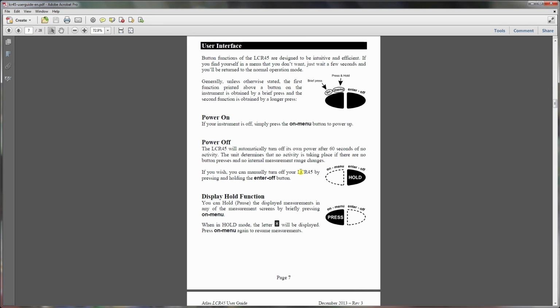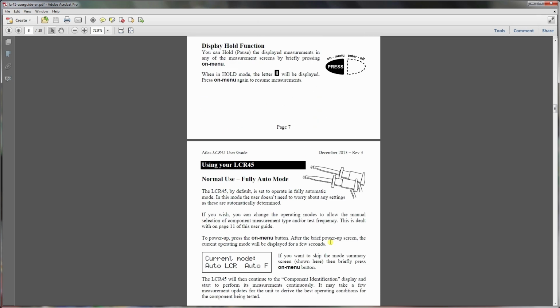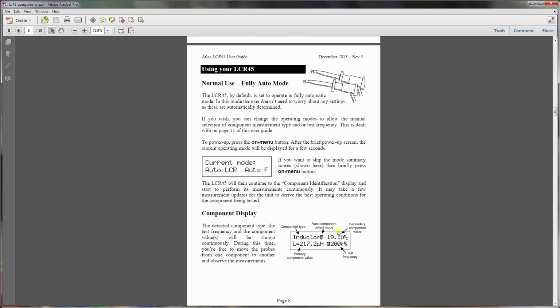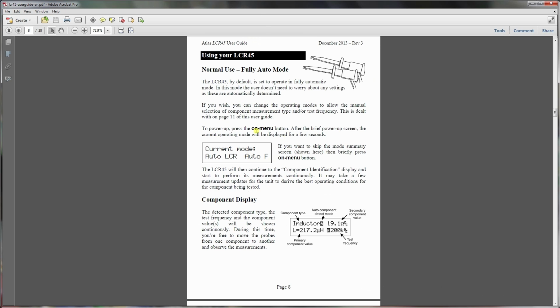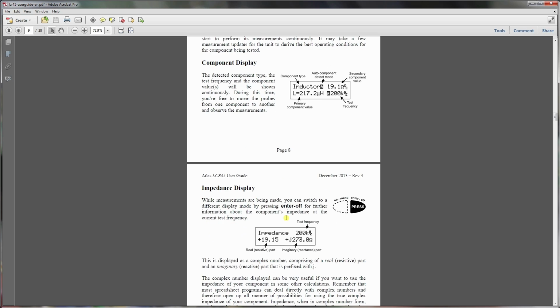And then we can have a quick look through the manual. So the manual shows you how to turn on and off the device, how to hold the display. So you'll notice that the display was constantly updating, but if you didn't want it to change, you can hold the display and it will just fix what's displayed on there. And then you have the various modes. So we were using it in fully automatic mode, and that automatically detects what the component is attached to the device, and then it gives you the various screens.